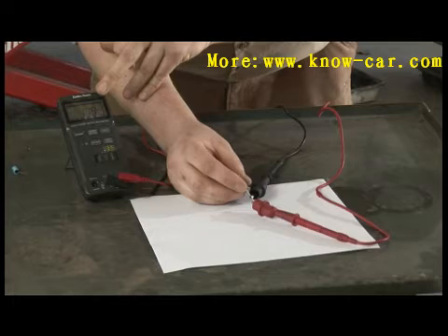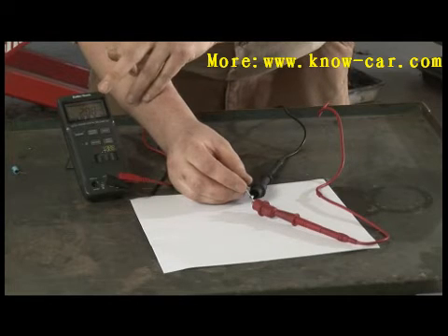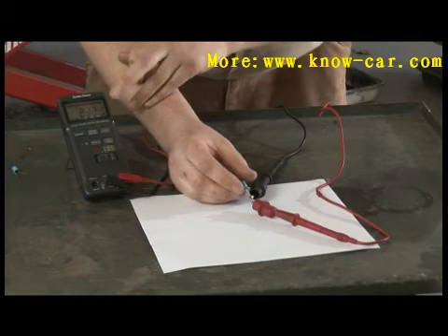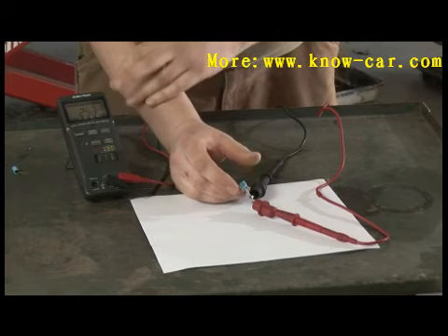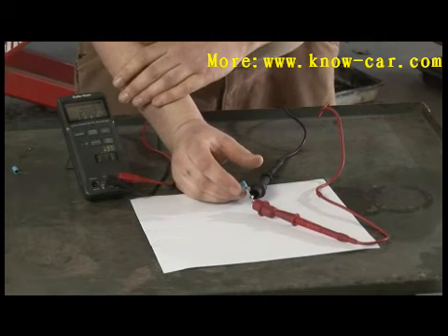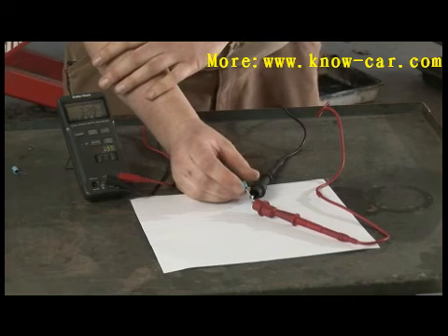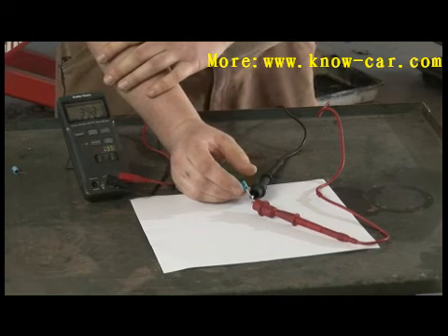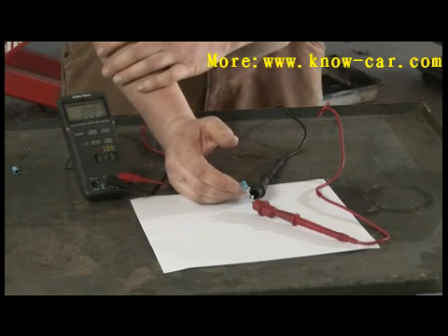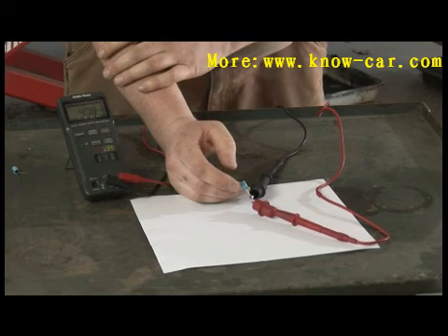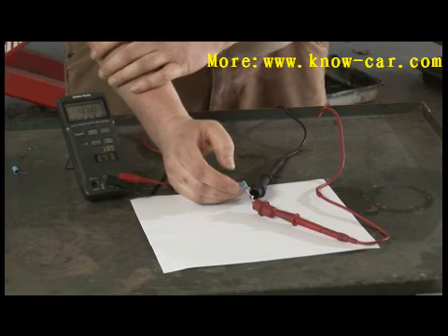If you see this resistance increase, then that means that the capacitor is functional. If you see infinite resistance or just a static resistance, even though the capacitor had been fully discharged, then that's a good indicator that the capacitor has a problem and should be replaced.